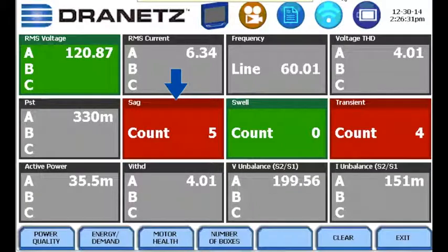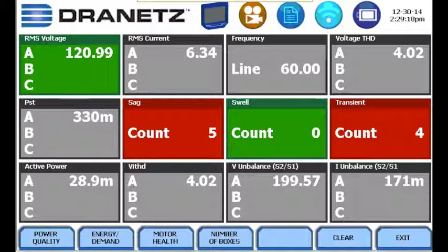The count indicates the number of times that event has occurred since monitoring has started. For all other parameters including THD, power, and other parameters, a yellow color indicates that the parameter has crossed the high or the low limit and the red color indicates that the parameter has crossed the very high or the very low limit.